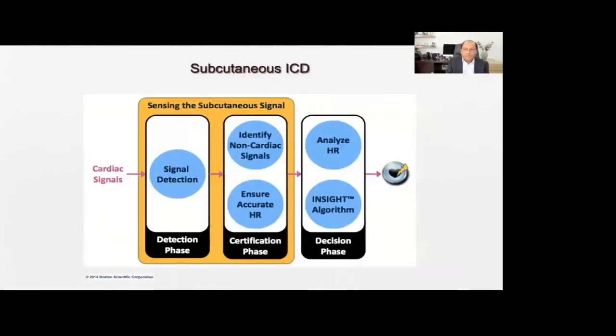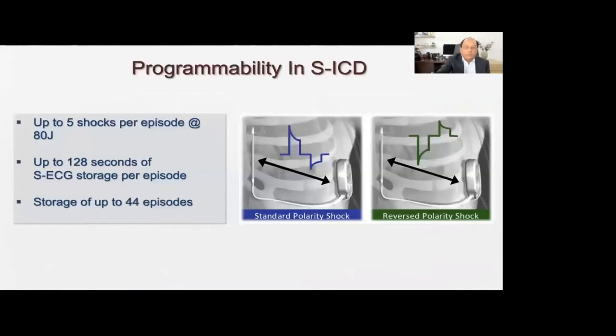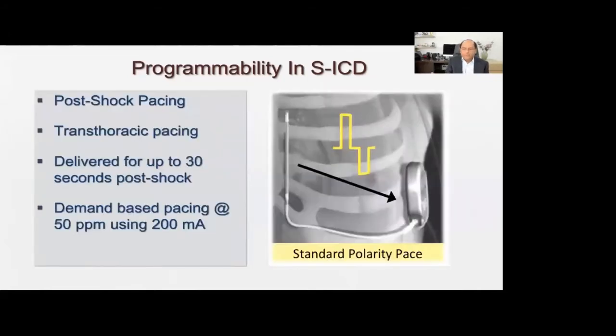So the SICD has a very simple working algorithm. First, there is a detection phase in which the cardiac signal is collected. In the certification phase, the device eliminates non-cardiac signals and ensures accurate heart rate. And the last phase is called the decision phase, where it analyzes the heart rate to decide about the tachycardia and applies the InSight algorithm for SVT discrimination if required. The device delivers up to 5 shocks per episode at a fixed output of 80 joules. There is up to 128 seconds of ECG storage per episode, and up to 44 episodes can be stored. As I said earlier, there is post-shock pacing, which is basically high energy transthoracic pacing consisting of 200 mA pulses, and it can be delivered for up to 30 seconds.